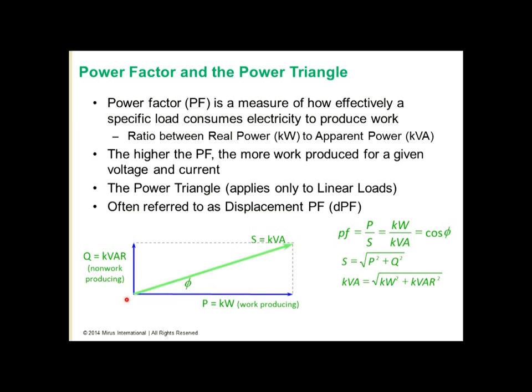The inductive component or capacitive component of reactive power is shown on the y-axis, inductive being upward and capacitive being downward typically. And then we have the real power in kilowatts on the x-axis. And the sum of these two vectors results in the apparent power in kVA. And there is an angle theta between the apparent power and the real power. Power factor is equal to real power divided by apparent power, or kilowatts divided by kVA, and is equal to the cosine of that angle theta. Apparent power is the square root of real power squared plus reactive power squared. kVA equals the square root of kilowatts squared plus kVAR squared.